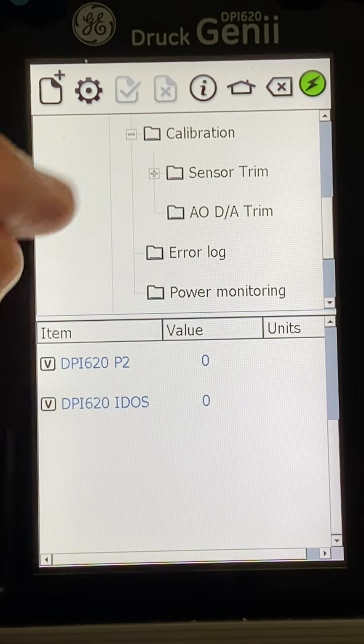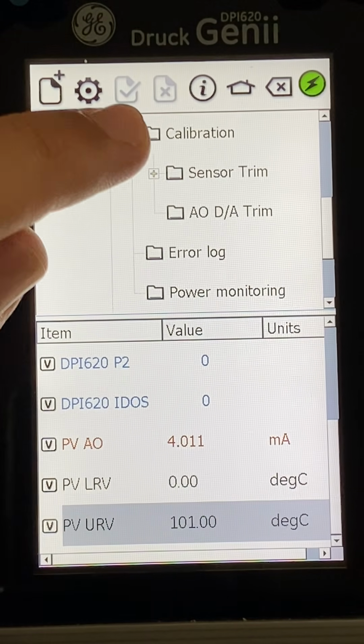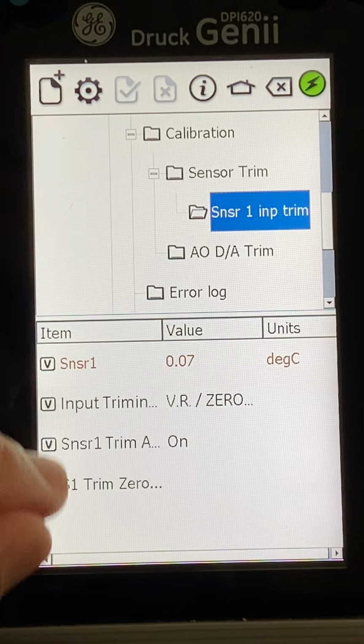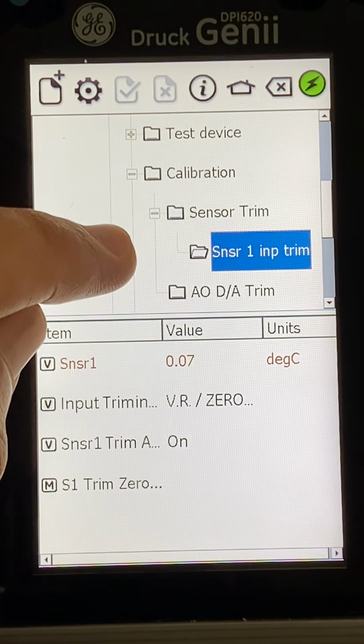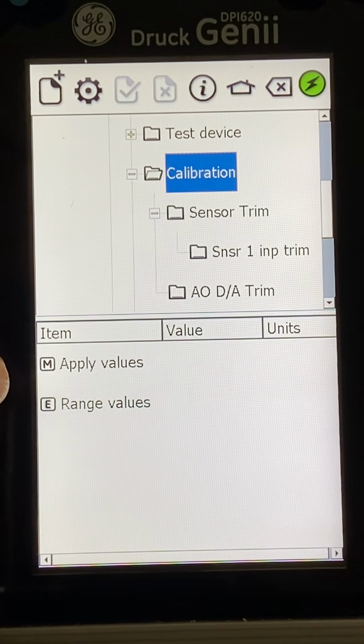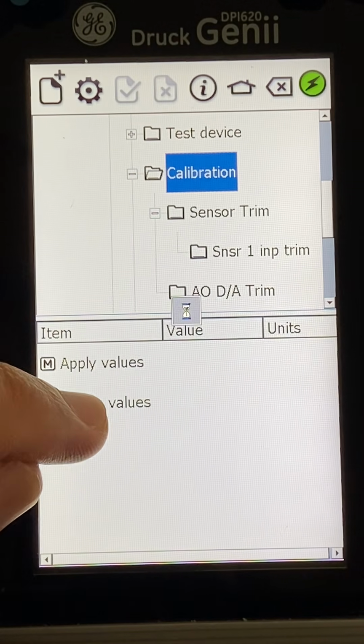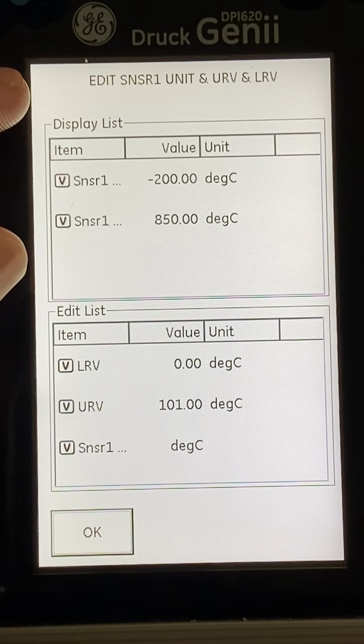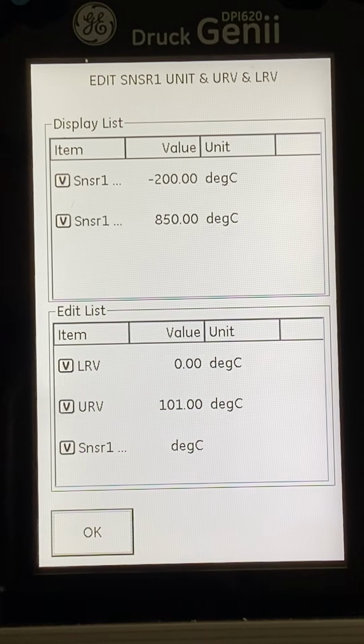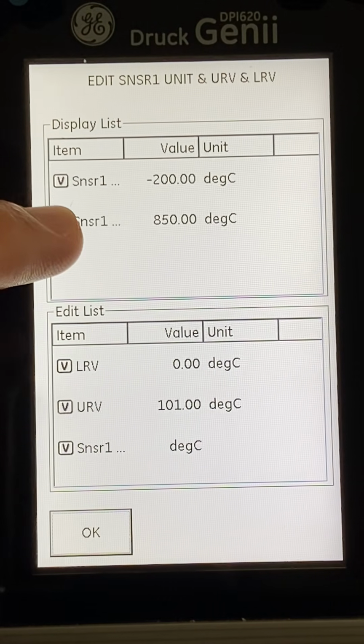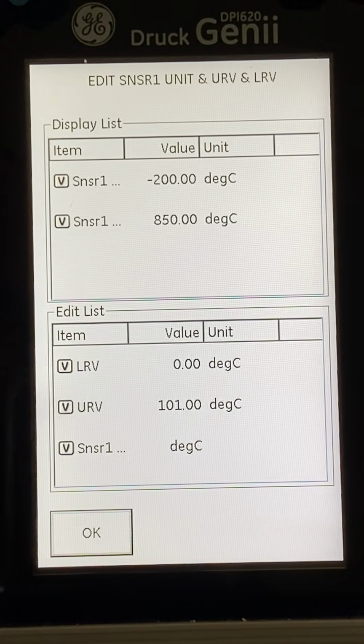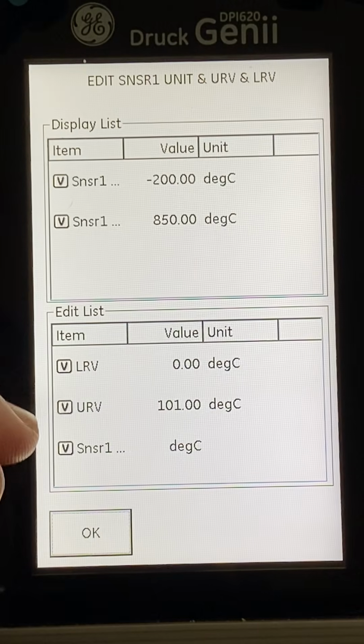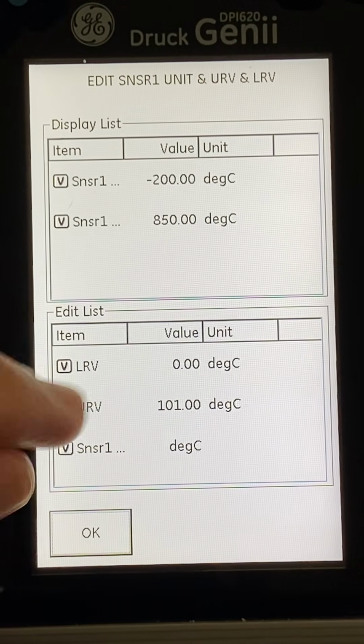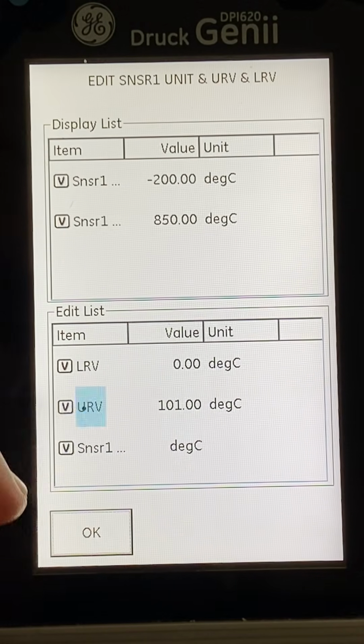I have calibration, sensor trim if I want to do a trim. So I have also a way to adjust. If I wanted to adjust the transmitter, I can simply do a trimming from here. So here is the option to do the trim on the transmitter sensor. Let me go to calibration. See, I can apply values or range values. The range values will give me the limits of the transmitter. So the minimum is minus 200, the maximum is 850. These are the minimum and maximum settings for the channel. And here I can edit the readings or edit the LRV, URV by the key input as we did in the previous exercise.